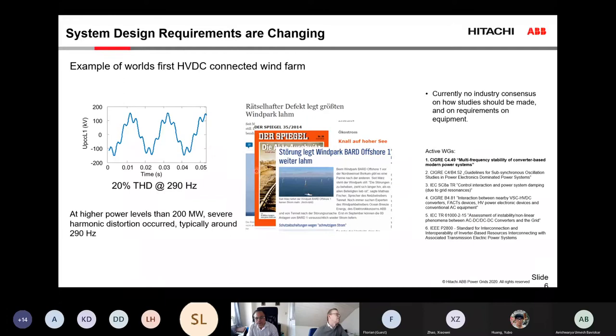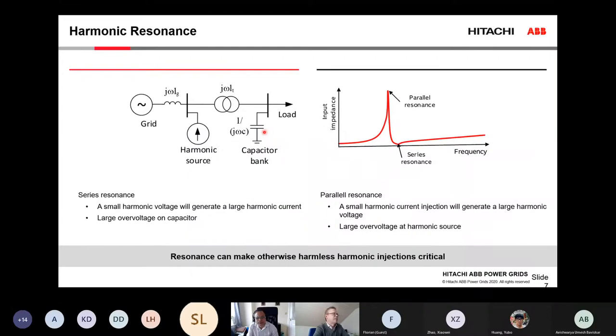So let's first look into how these things can happen. First we need to understand this concept of harmonic resonance. You can look at this figure where we have a grid connection. We have some grid impedance there. We may have a transformer, for example in a distribution grid, and a capacitor bank here for power factor correction. When we connect devices to this system, for example generators or converters injecting current into the network, we always connect them in a physical location. And from each of these physical locations, the input impedance will look different. So we can calculate here this input impedance seen from the harmonic source.